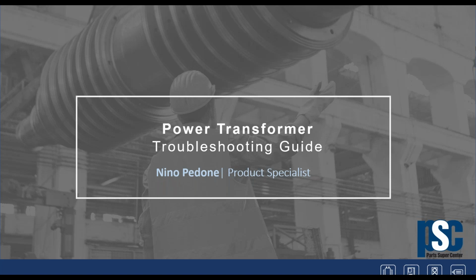From the title of what we have to speak about, we're going to start with power transformer. First off, I want to clarify one thing. The power transformer does not transform power, but transforms the components of the power. In other words, the electric power is a multiplication between the voltage and the current. So what the transformer does, from one winding to another, it changes the components. In other words, if the voltage goes up on one side, the current must go down. On the other side is the opposite. So again, we call it power transformer, but it does not transform power, but transforms the components of power.